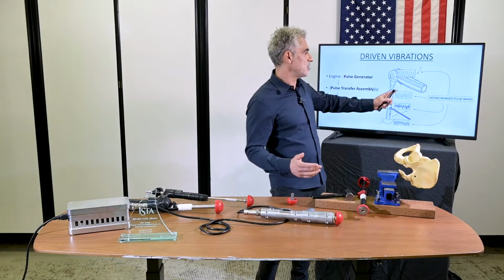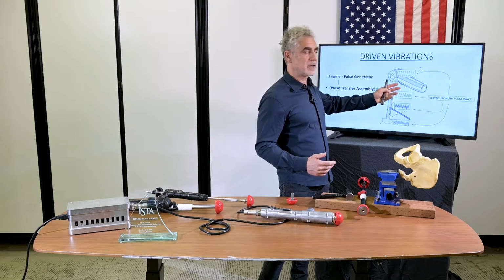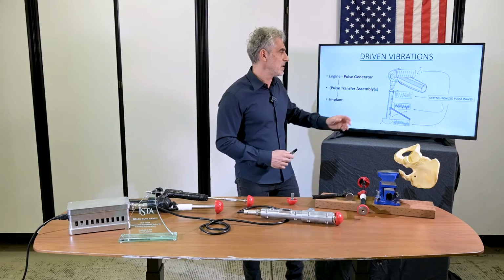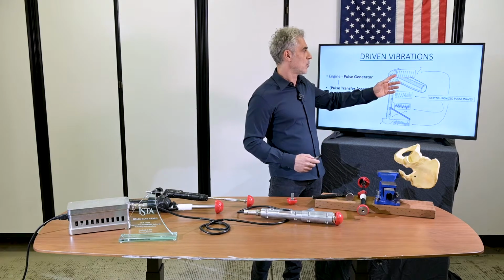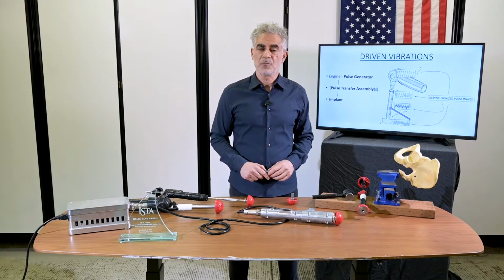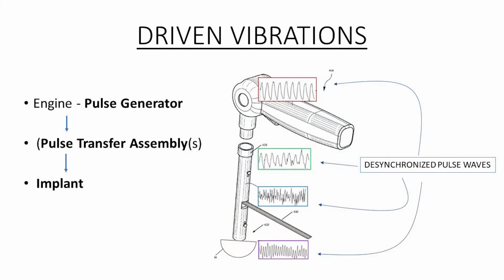It uses an oscillation engine to create an original pulse wave. This pulse wave has its own amplitude, frequency, wavelength, and direction. This wave then transfers through a series of supports and creates a series of secondary pulse waves. These secondary pulse waves eventually reach the implant and create vibration of the implant, which allows the implant to be installed into bone without impacts. There's a desynchronization process of the oscillations that occurs between the supports, and each desynchronized pulse wave develops its own pulse frequency, wavelength, amplitude, and direction.